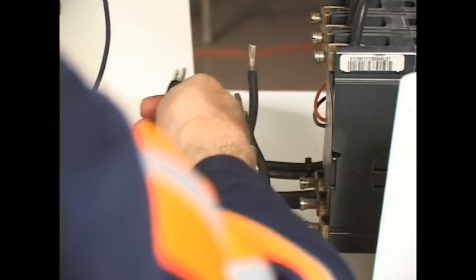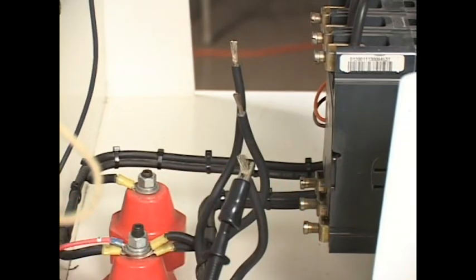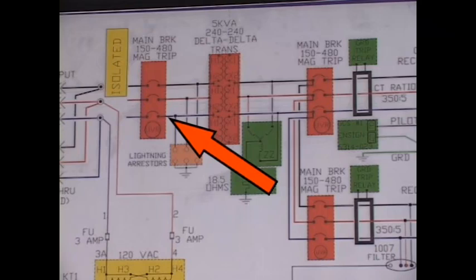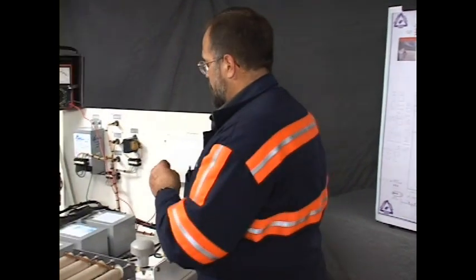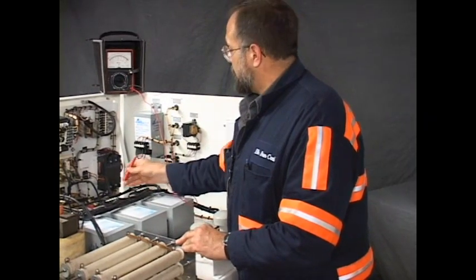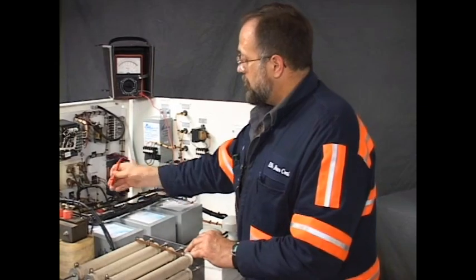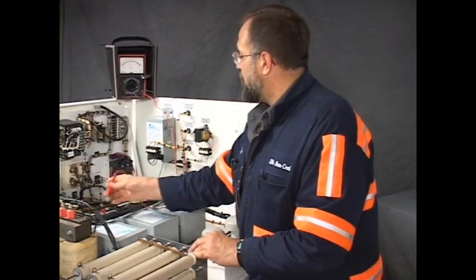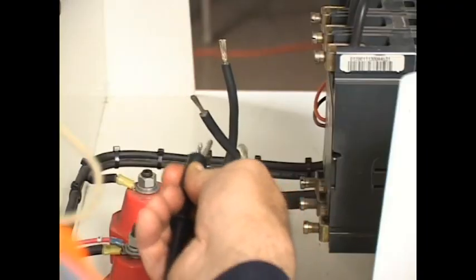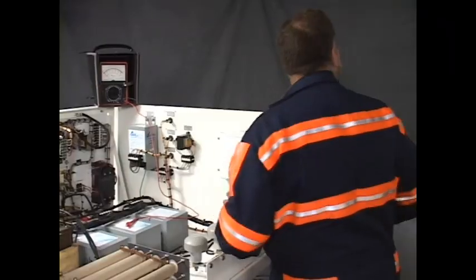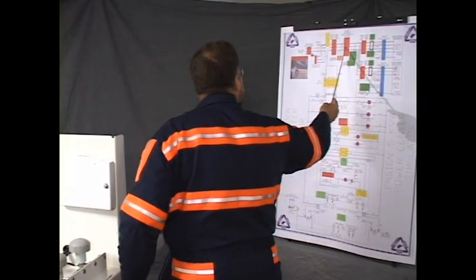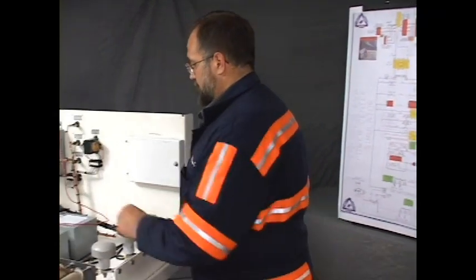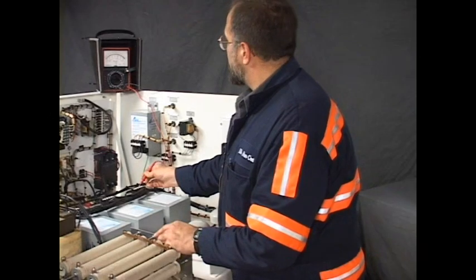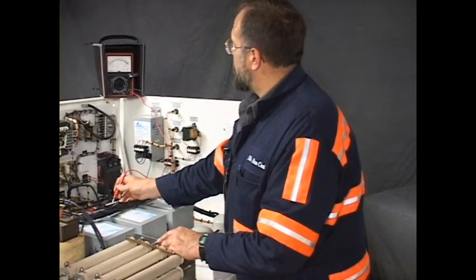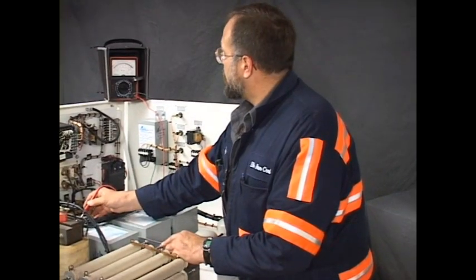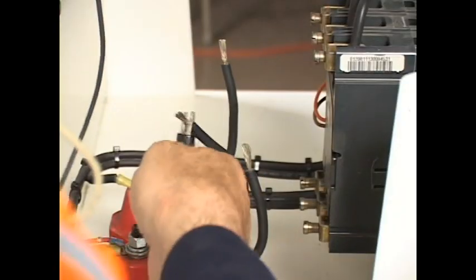I'm going to attach my black lead to the first phase, right here. I'm going to read to the delta-delta transformer. And we have continuity. To the second one, we have continuity. And to the third one, we have continuity. Move our test lead to the middle phase. That's right here. I'm attached here, reading to these 3 points. To the first phase, I have it. To the second one, I have it. And to the third one, and I have it. All right, we have one more phase.